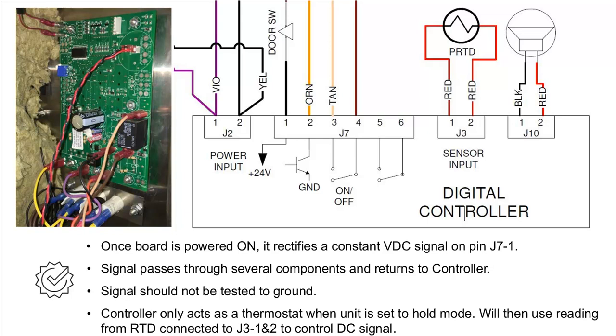Back to the control board. When the control board is powered on, it rectifies a DC signal, 24 volts. The output is here on J71. The return or ground is here on J72. This means this is not a grounded circuit. You cannot test this circuit to ground. It must be done wire to wire within the circuit itself.